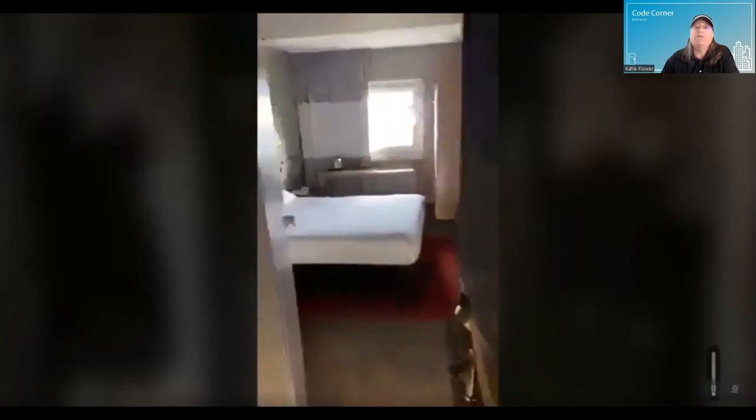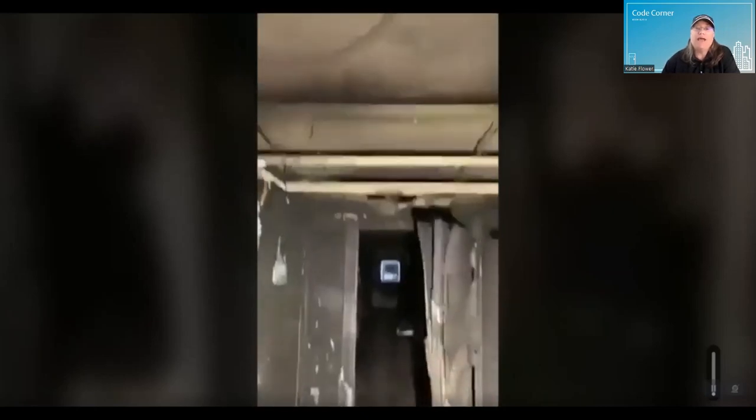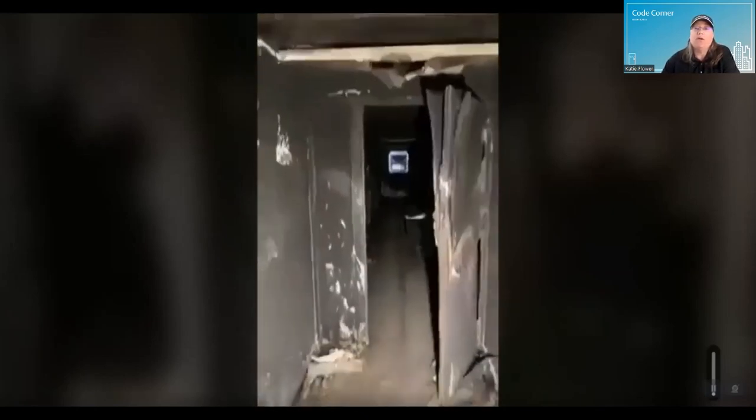This is a video of a 20 minute rated apartment door after a fire. You can see the hall is black and covered in soot. When the apartment door is open, it looks brand new and untouched by the fire and smoke. Thank goodness this door was closed and latched at the time of fire like it was supposed to be.